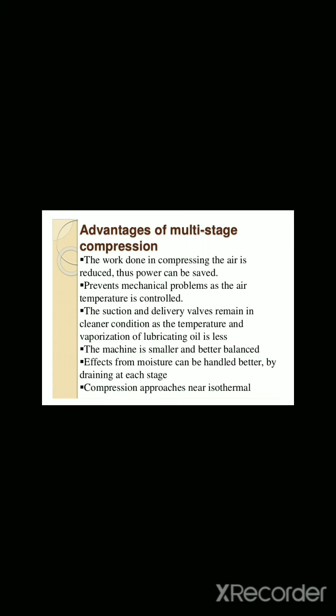Firstly, we have to see the advantages of multi-stage compression. The work done in compressing the air is reduced, and thus power can be saved. This is the first advantage. Second, it prevents mechanical problems as the air temperature is controlled. Third, the suction and delivery valves remain in cleaner condition as the temperature and vaporization of lubricating oil is less. The machine is smaller and better balanced. Next, effects from moisture can be handled better by draining at each stage. Last one is compression approaches near isothermal.